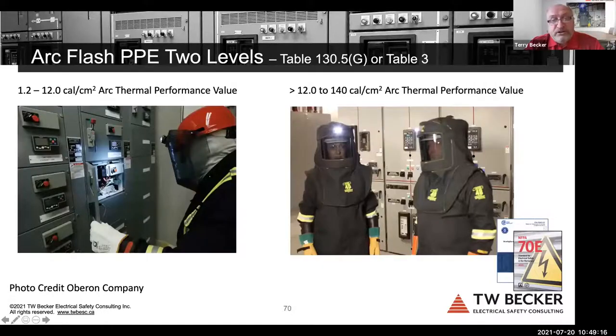You can see our faces through that shield, and the LEDs on the arc rated face shields. You can see that it's lighting up that MCC starter bucket, and you can move it with your head. So the LEDs, again, the hood ventilation system, still I find arc flash suits with no hood ventilation systems. You got to get the hood ventilation system.